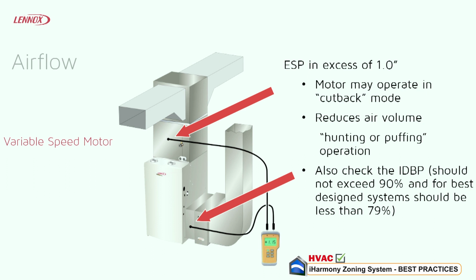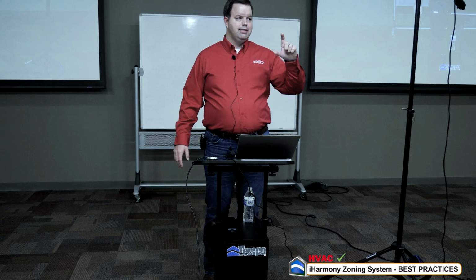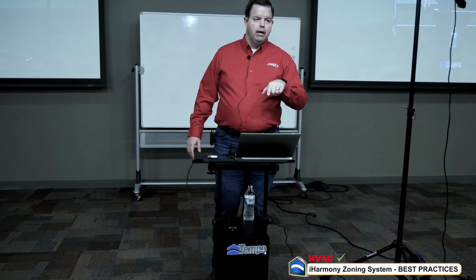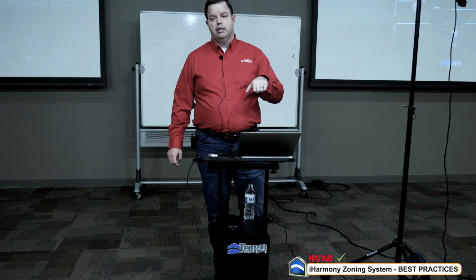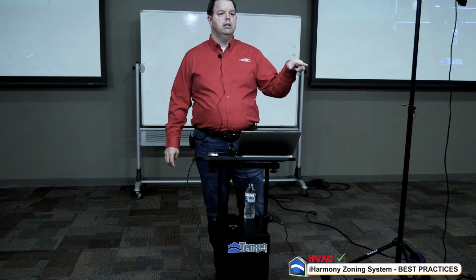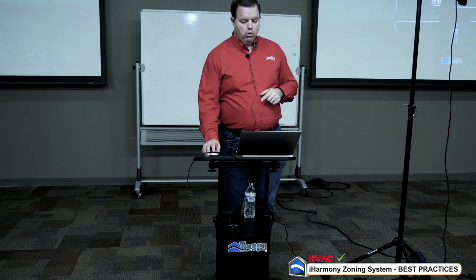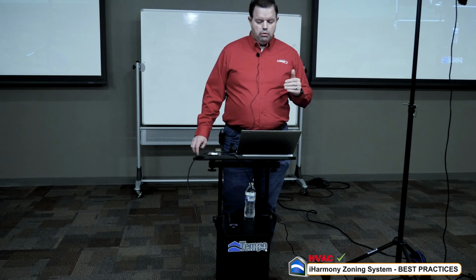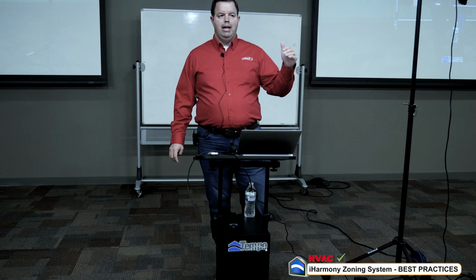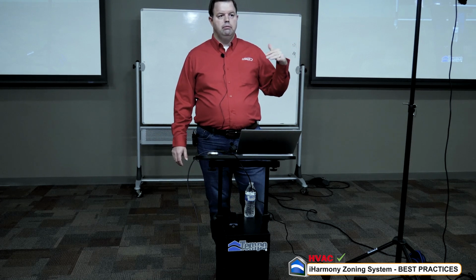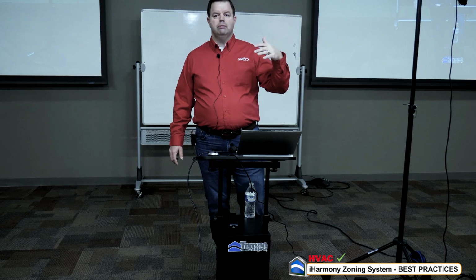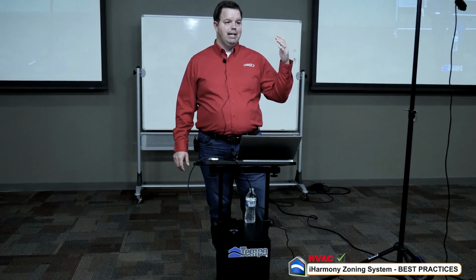Yeah, one thing that you can do here is I always tell guys, run those zones individually on their own, and then you can go into the diagnostics for the zone board. You go in the installer setup, in that diagnostics tab, just check the zone board, and in that diagnostic screen, or rather, I'm sorry, not the zone board, but your furnace or your air handler. And in that diagnostic screen, it's going to give you indoor blower power. So really we want to keep that, like it says here, below 79%. If you're up in the 80s and 90s, that's an indication of high static.